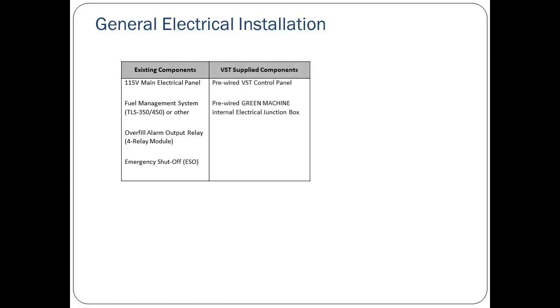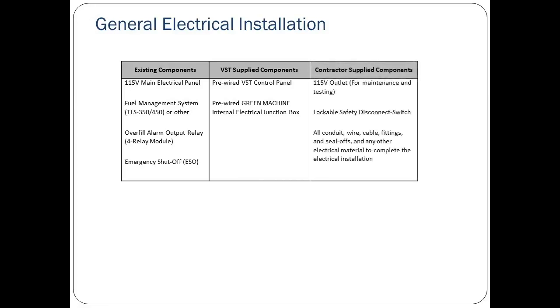VST will supply the control panel, which comes internally pre-wired from the factory. Also internally pre-wired is the Green Machine internal junction box, which sits in the middle of the Green Machine vapor processing unit. The contractor is responsible for supplying an outlet and a disconnect switch, both to be installed next to the Green Machine unit. The contractor is also responsible for all general installation and components, including conduit, wire, cable, fittings, seal-offs, and any other components deemed necessary.